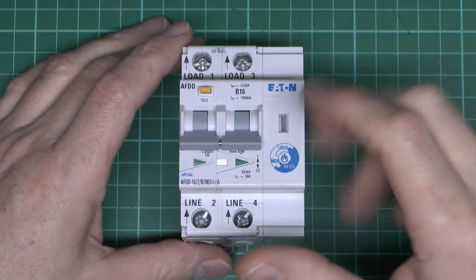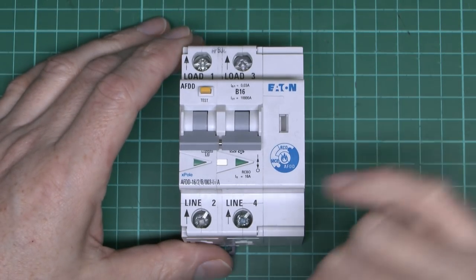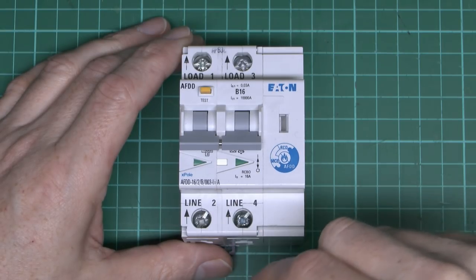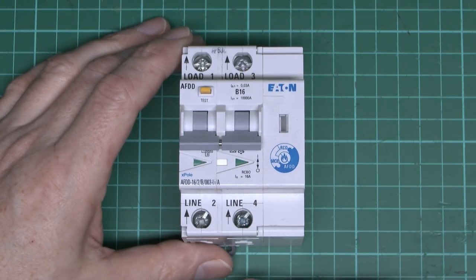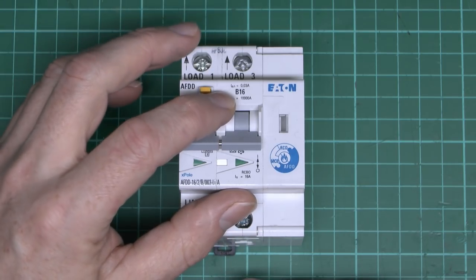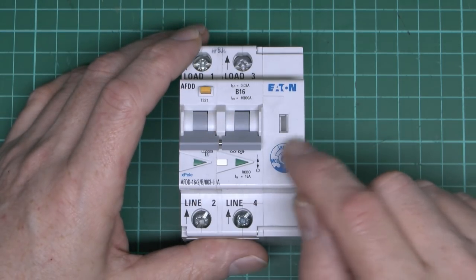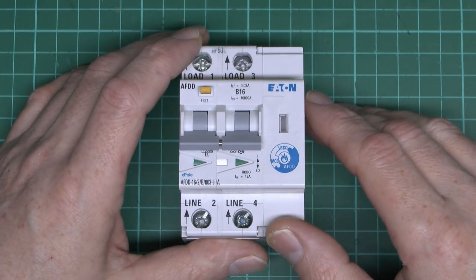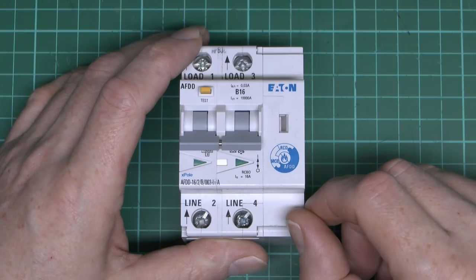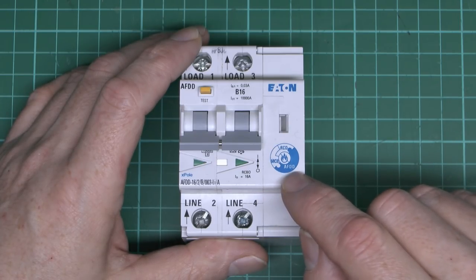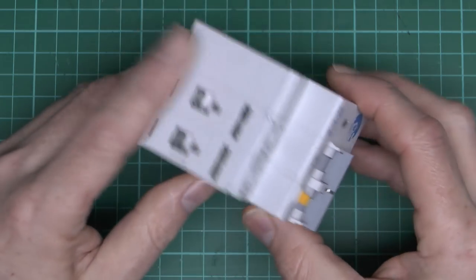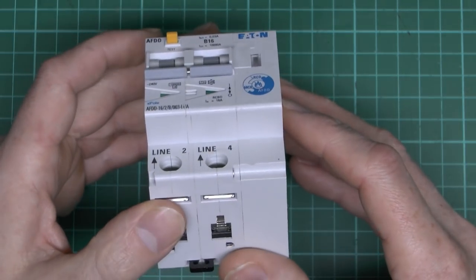Now let's just have a look at what we've got here. This is sort of a 3-in-1 device, as it's got here on the side. Basically this is an MCB, or one that trips on short circuit and overload. In this case it's a 16A type B. And it's also an RCD, so that detects whether there's an imbalance between the line and neutral there. It's a 30mA type, fairly standard deal. And also it's got the AFDD functionality as well. So basically it's a 3-in-1 device, and this is intended to supply a single circuit.